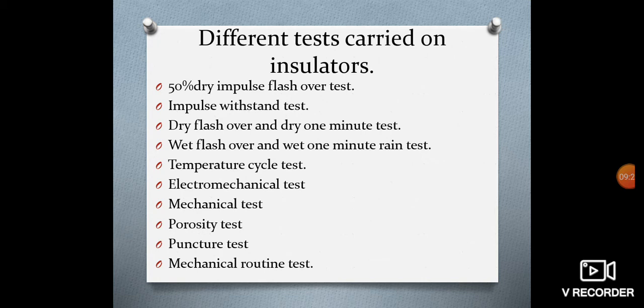Then electromechanical test. The test is carried out only on suspension or tension type insulators. The insulator is subjected to 2.5 times the specified maximum working tension maintained for 1 minute. Also, simultaneously, 75% of the dry flashover voltage is applied. The insulator should withstand this test without any damage.